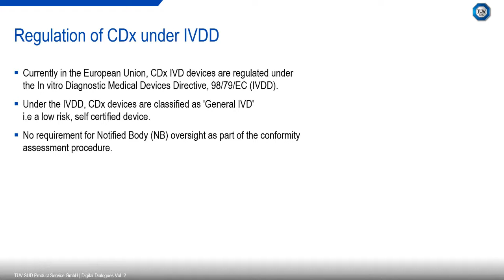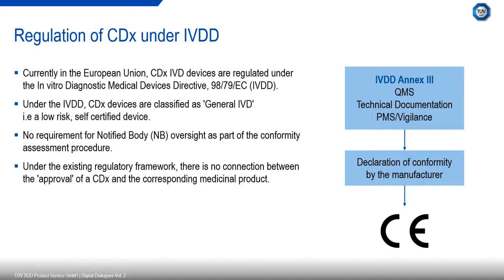So currently, a manufacturer will follow the conformity assessment route described in Annex 3 of the directive. They will need to have a QMS which is in compliance with the directive. They will prepare their technical documentation, have systems and processes in place for PMS and vigilance. The manufacturer will then prepare their declaration of conformity, and the device is CE marked. So this is how it currently is. However, as I'm sure everyone is very well aware, the directive will be replaced by the In Vitro Diagnostic Regulation, or IVDR, becoming fully effective on the 26th of May next year. So we're effectively 1 year away from that date of application.